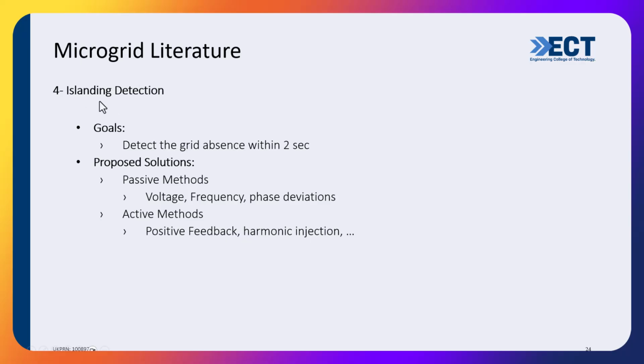So we have to detect that islanding is happening, that there is a grid absence or grid failure, to isolate ourselves from the grid and work locally in island mode. So we want to detect the islanding in order to work in island mode, not grid-connected mode, and change the mode. The goal is to detect the grid absence within 2 seconds. Why 2 seconds? Because this is the IEEE standard. They have to detect the islanding, or grid absence or failure, within 2 seconds only, and then switch to island mode.